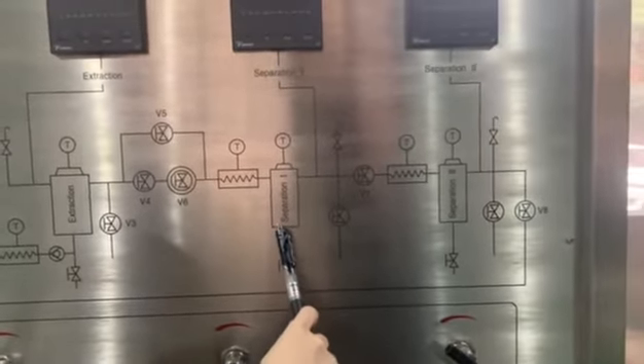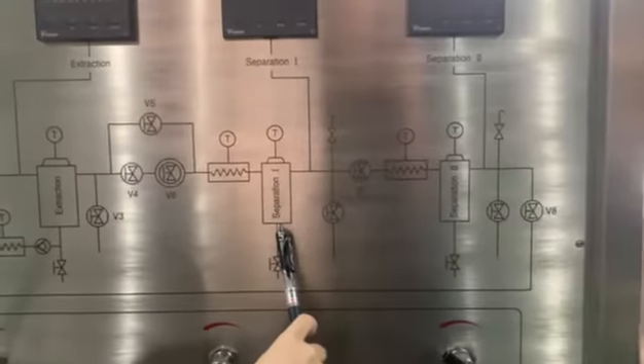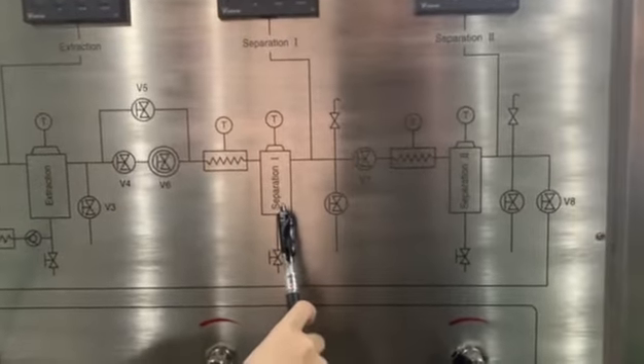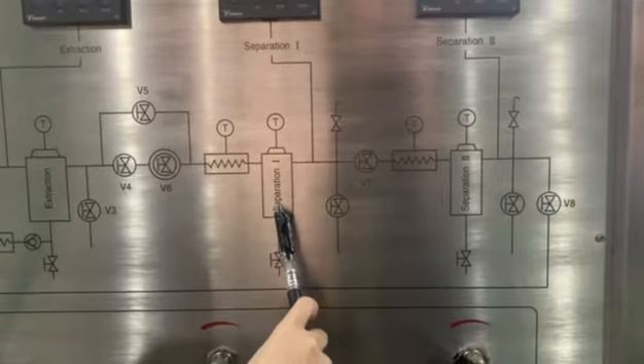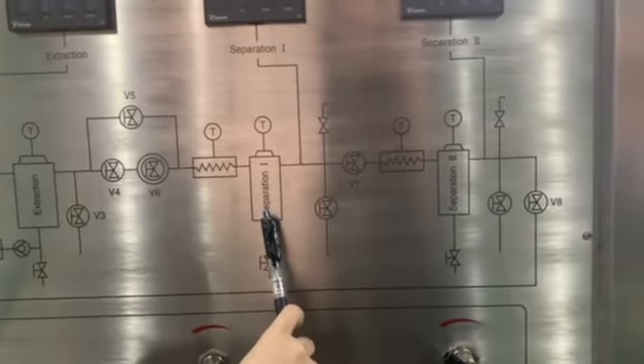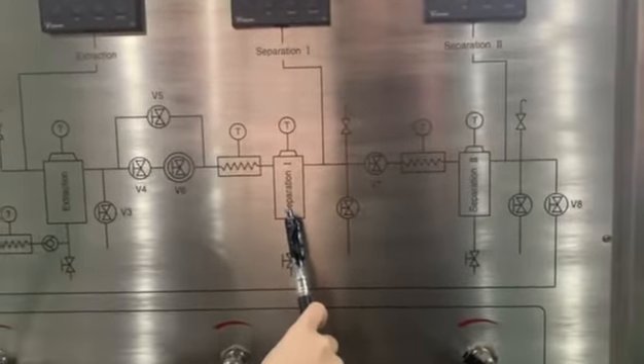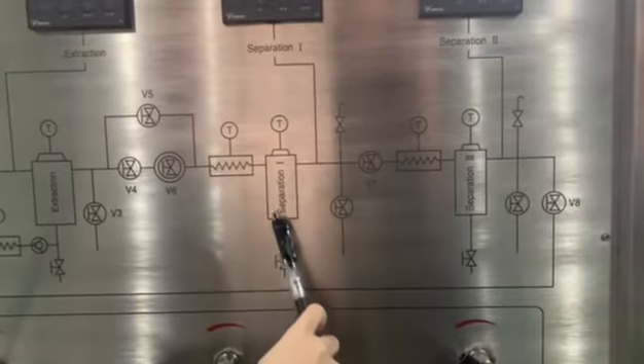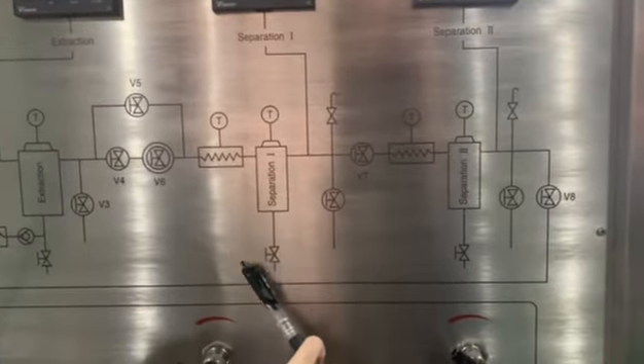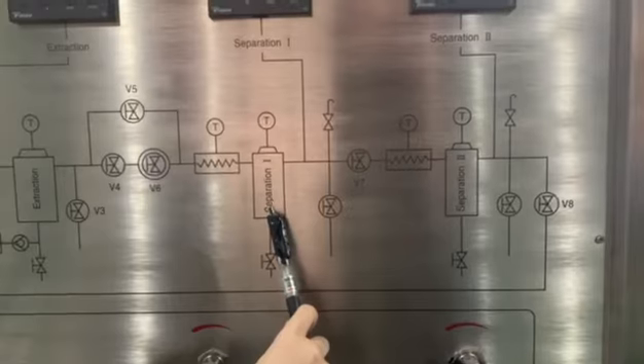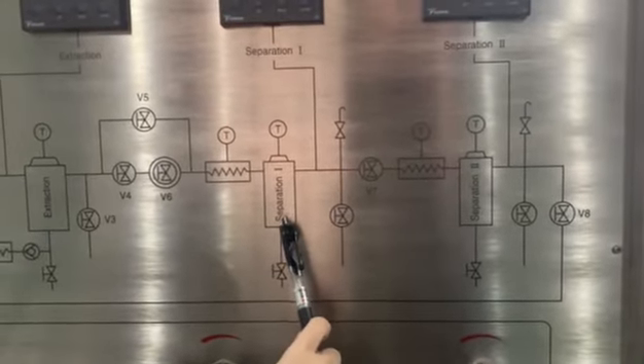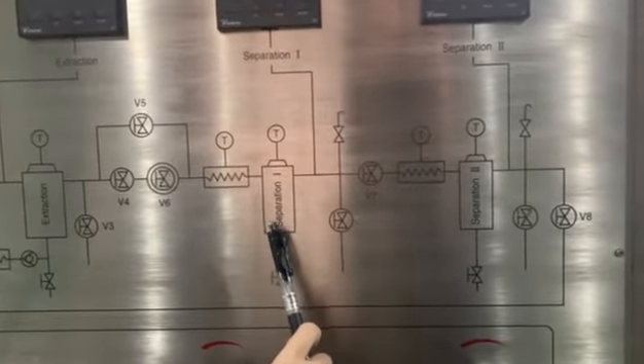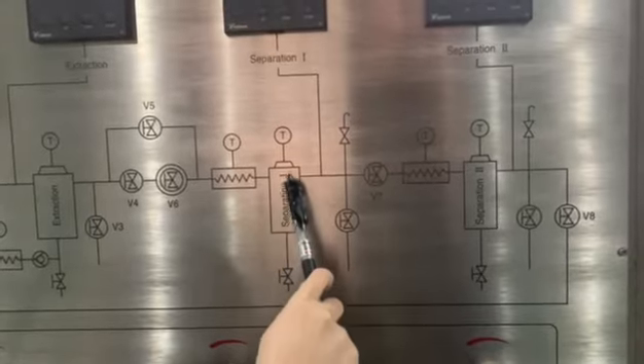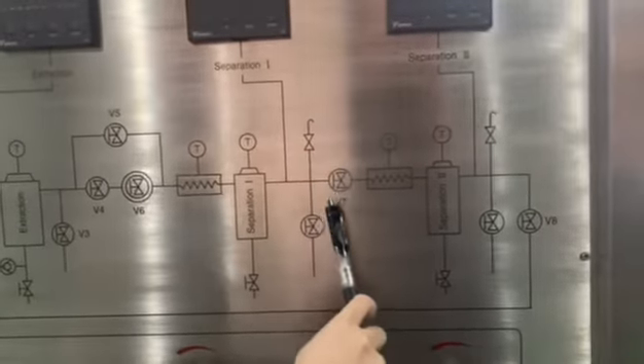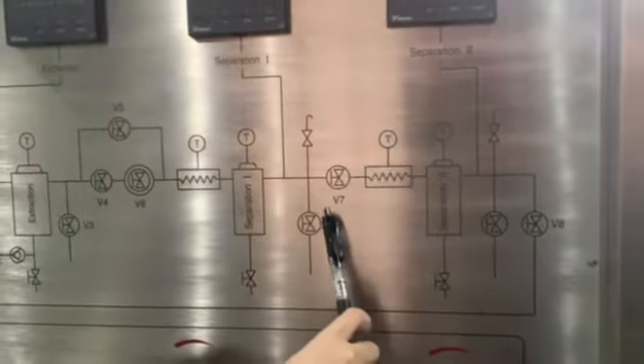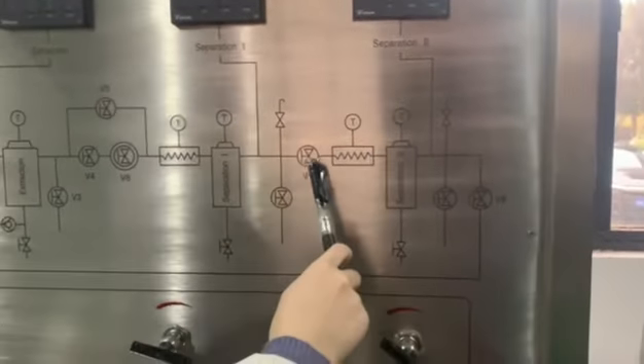The process conditions of the first stage separation kettle are controlled to separate the CO2 from the extraction mixture. The CBD paste is removed from the bottom of the separation kettle. The mixture that does not meet the analytical condition is regulated by the high pressure control valve of the first separation kettle to enter the second separation kettle.